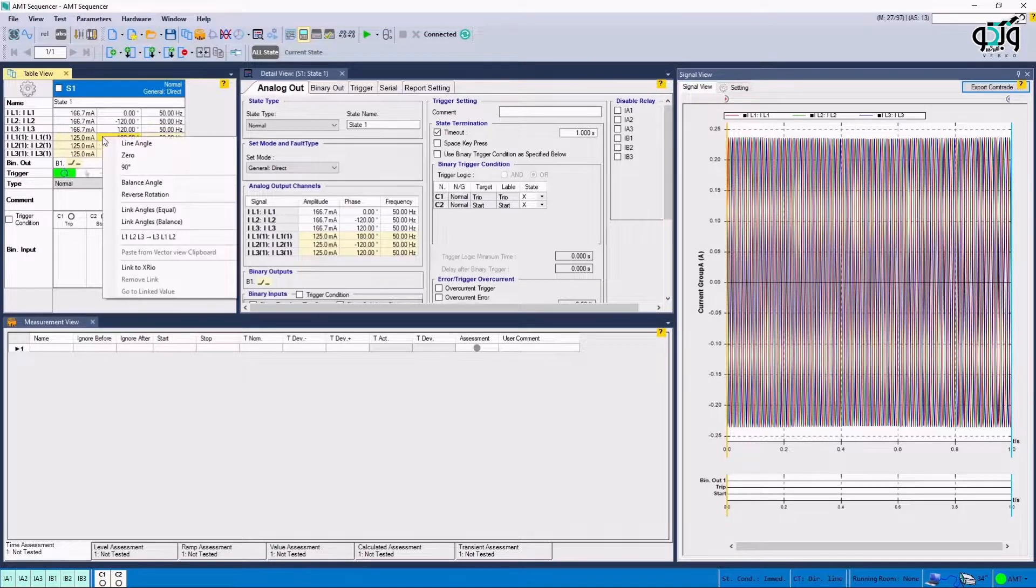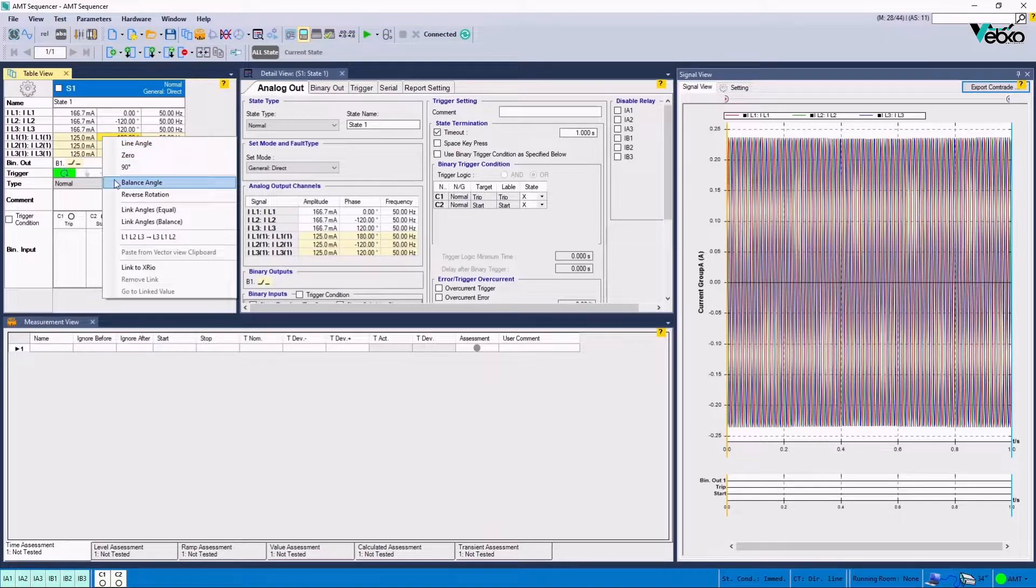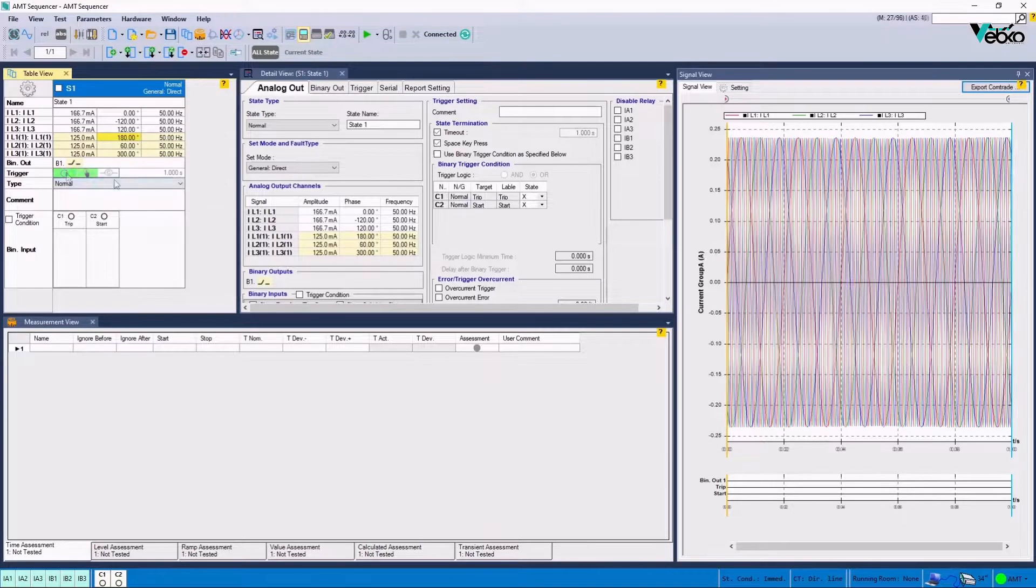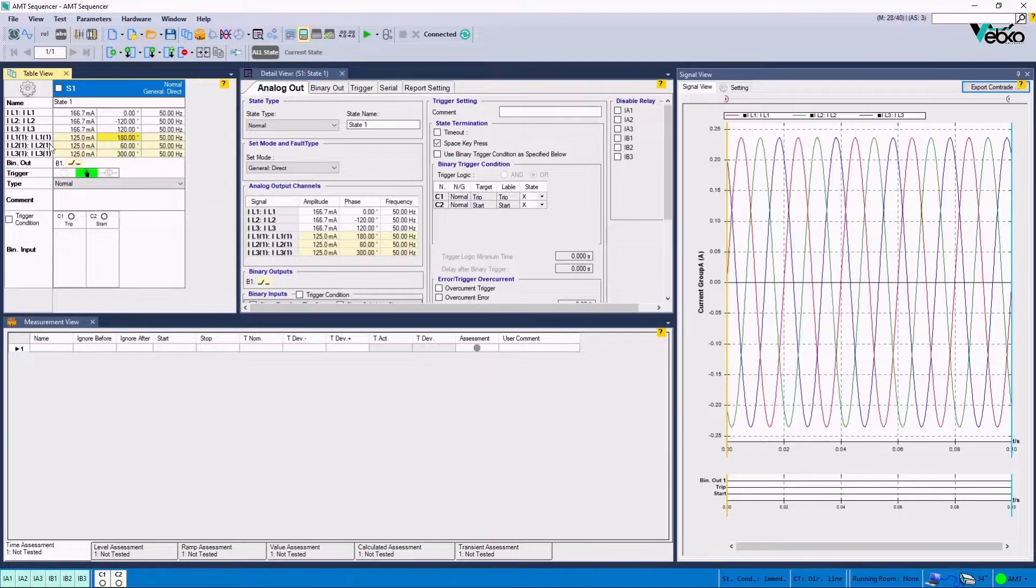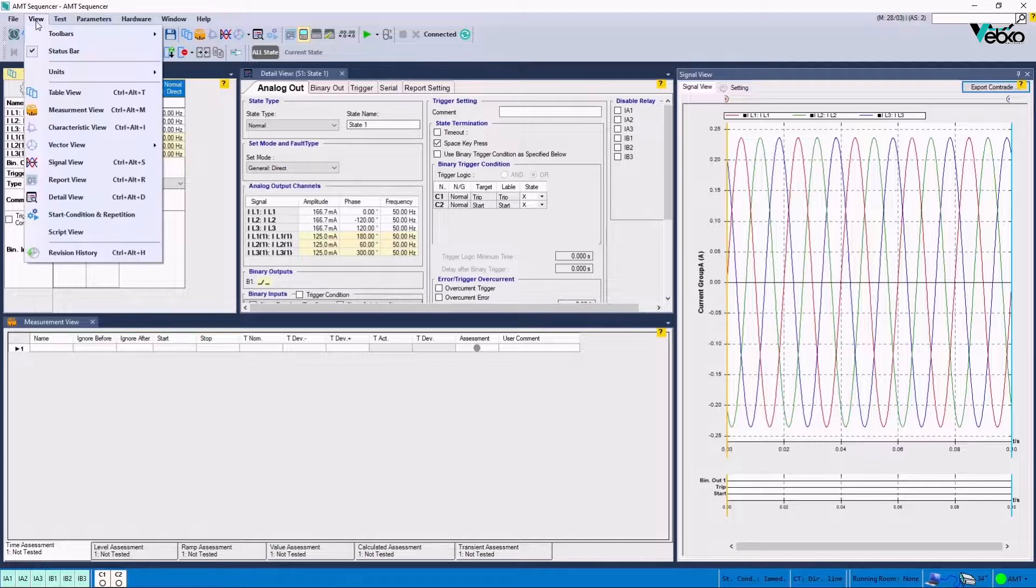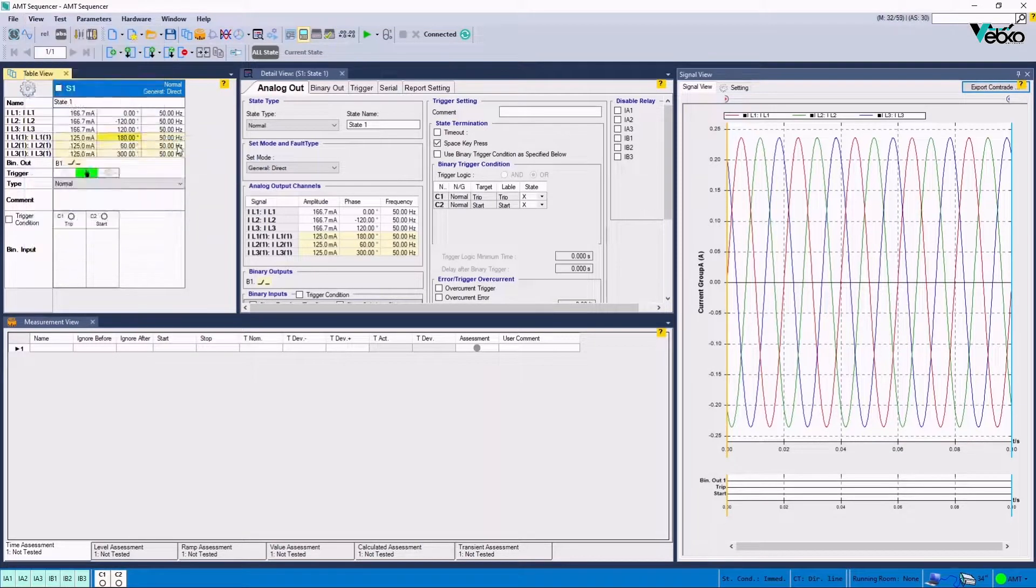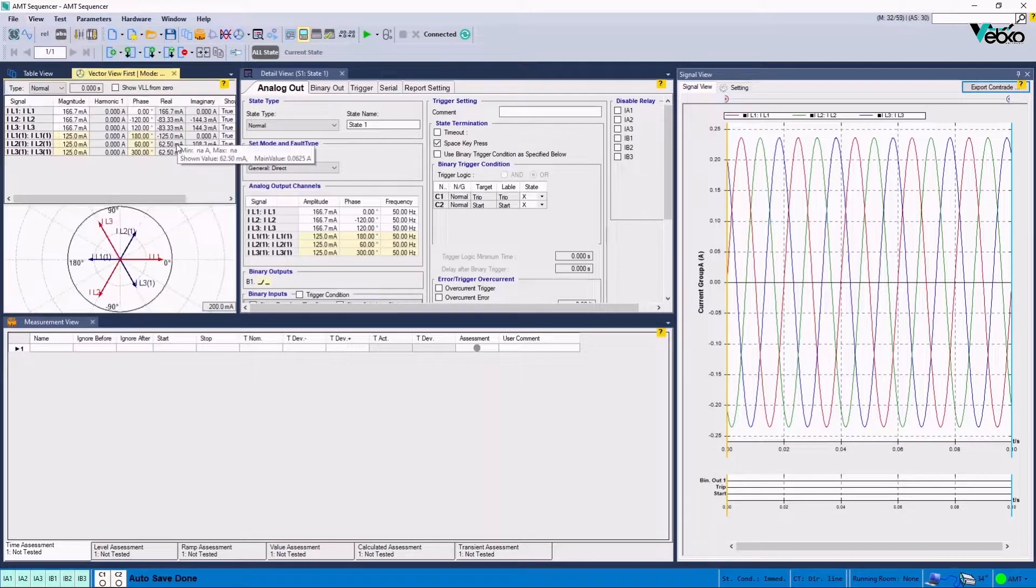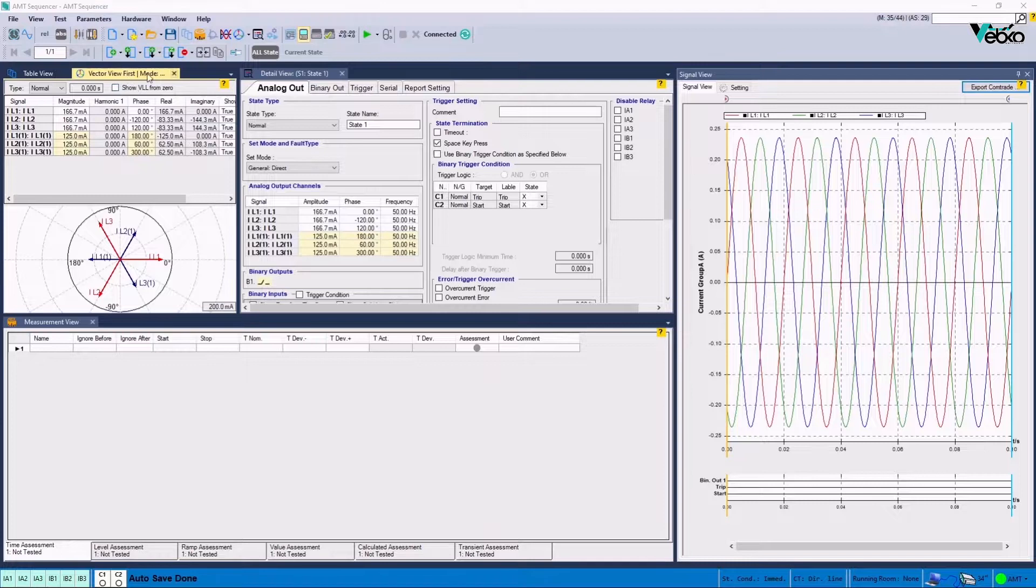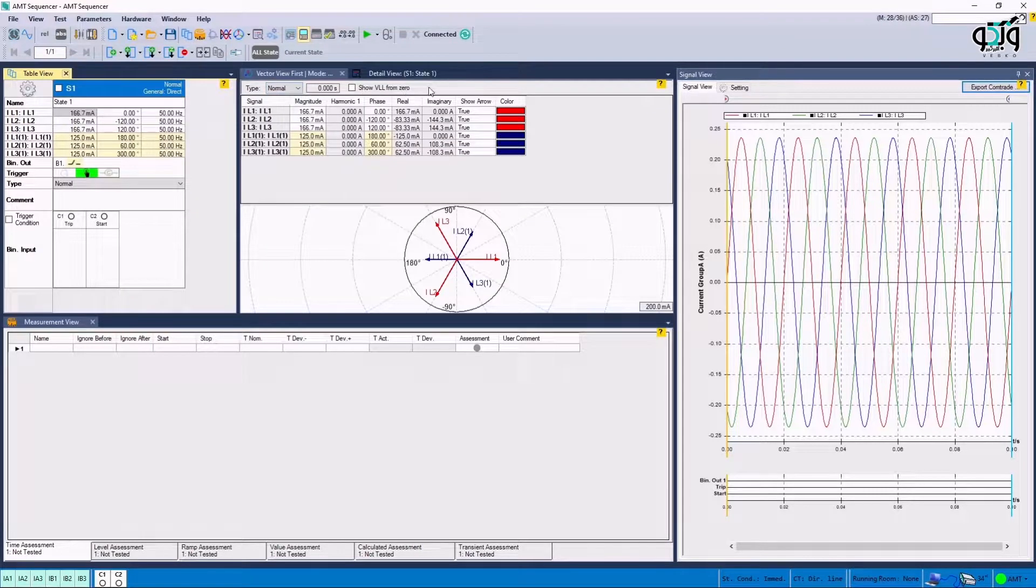To do so, the current angle of one of the cells is entered, and Balance Angle option is used to apply the angle difference for the other phases. It is possible to view the amount and direction of the current values in Vector View window. It should be noted that in Signal View window, it is possible to view the applied changes instantly.